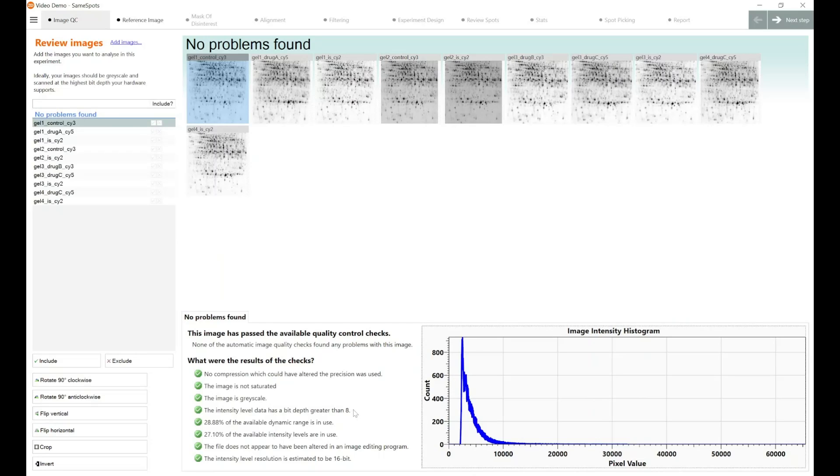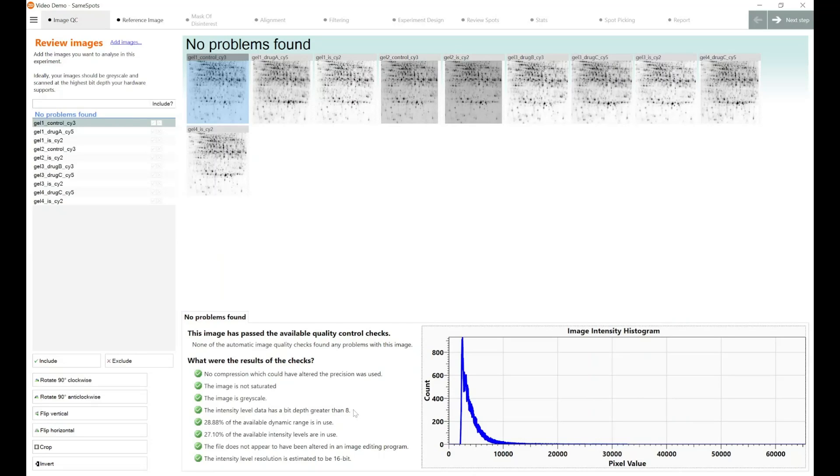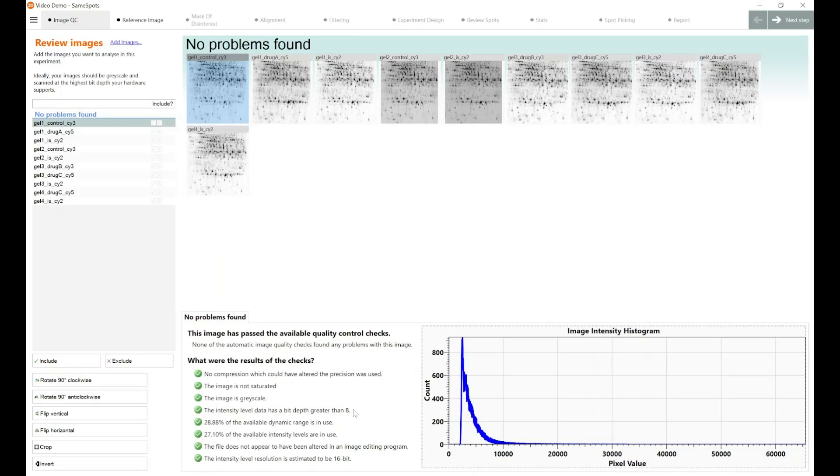For every level, for every bit depth level above that, you get exponentially more pixel values that that pixel could be. So you've got a much greater range in which your data could lie. We recommend, and I believe every modern gel documentation device will export to 16-bit TIFF images. So with a 16-bit image, you can get around 65,000 different pixel intensity values per pixel. So it gives you this much greater range of sensitivity to detect small differences between different spots based on their pixel intensity value. We would always recommend a 16-bit TIFF if your gel documentation device allows. If not, always go for the highest bit depth image you can, just to capture more data and have more sensitivity when it comes to your analysis.